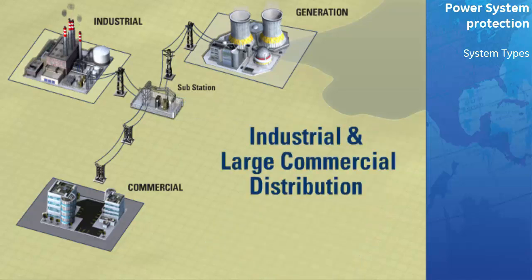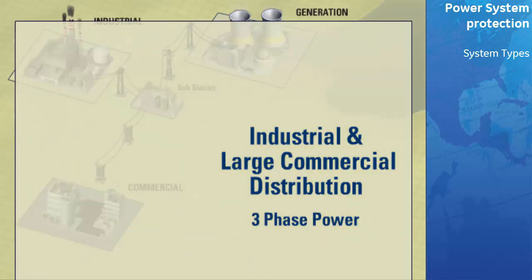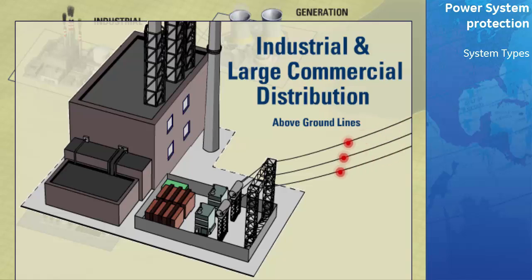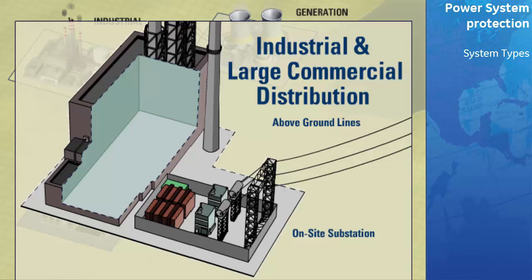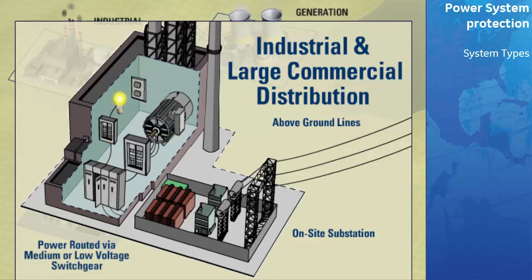The distribution system for a typical industrial or commercial user shares some similarities to that of the residential customer, with the major exception that the power being delivered is usually three-phase. From the substation, the industrial or commercial power lines take the power above or below ground to a large transformer, which steps the three-phase voltage down to a suitable level for the plant or building. For larger commercial or industrial users, this voltage may be in the medium voltage range, in which case there will be an additional substation on site. The power would then be routed from the transformer or transformers via medium or low-voltage switchgear to different areas of the plant or building for further distribution via switchboards and panel boards.